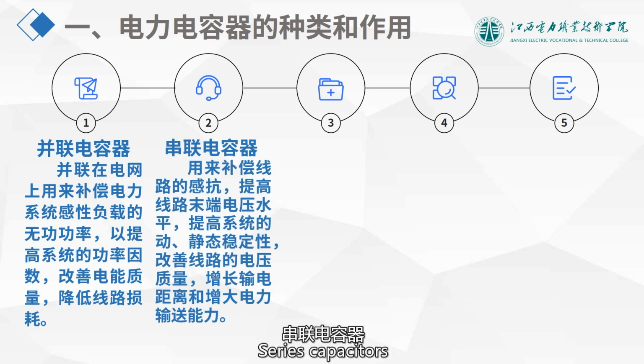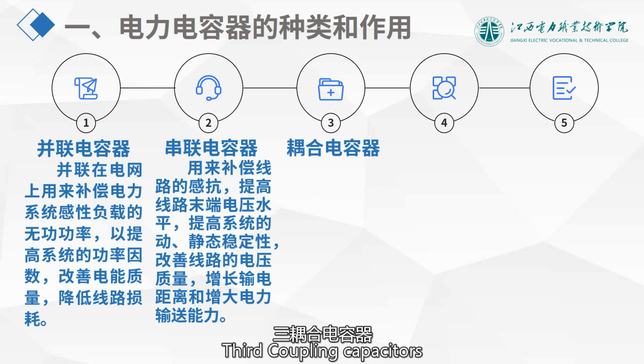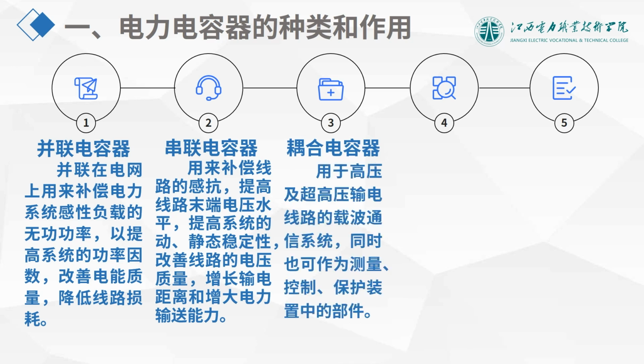Second, series capacitors. Series capacitors are mainly used to compensate for line reactance, improve the voltage level at the end of the line, enhance the dynamic and static stability of the system, improve line voltage quality, extend transmission distance, and increase power transmission capacity. Third, coupling capacitors.